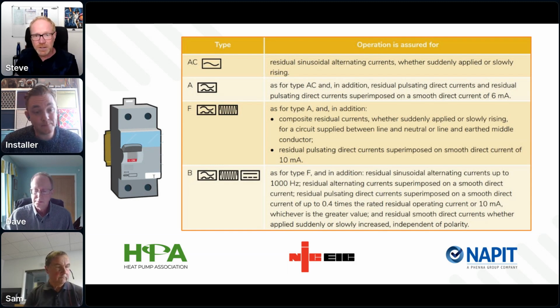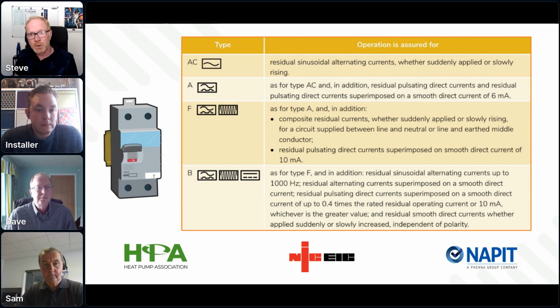And another reason, which obviously, as we're talking about safety and proper design, we wouldn't be doing the right thing for installers, as it's an installer show webinar, if we didn't talk about the economic reason. Type B RCDs can be much more expensive, sometimes 5 to 10 times higher than type As. So you think about the cost implication for a customer, which shouldn't be your first consideration. I do want to stress that. But for an installer, that is a consideration, and certainly for a customer. So where a type B is not needed, it's just an expensive bit of kit that you didn't need to install.